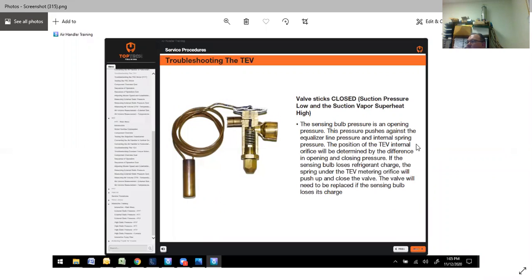Should the valve become jammed open and stay there, the valve will have to be replaced. Now here's what we typically see, or some combination of it, with the valve sticks closed. The sensing bulb pressure is an opening pressure. The pressure pushes against the equalizer line pressure and internal spring pressure. The position of the TEV internal orifice will be determined by the difference in the opening and closing pressures. If that sensing bulb loses refrigerant charge, the spring under the TEV metering device will push up and close the valve. The valve will need to be replaced if the sensing bulb loses its charge. It can, and it definitely happens. A lot of times it's self-inflicted, the expansion valve problems, but if your bulb loses the charge, that's where you're going to start up, and it's just your refrigerant is going to hit a brick wall. It's not going to flow through that expansion valve.